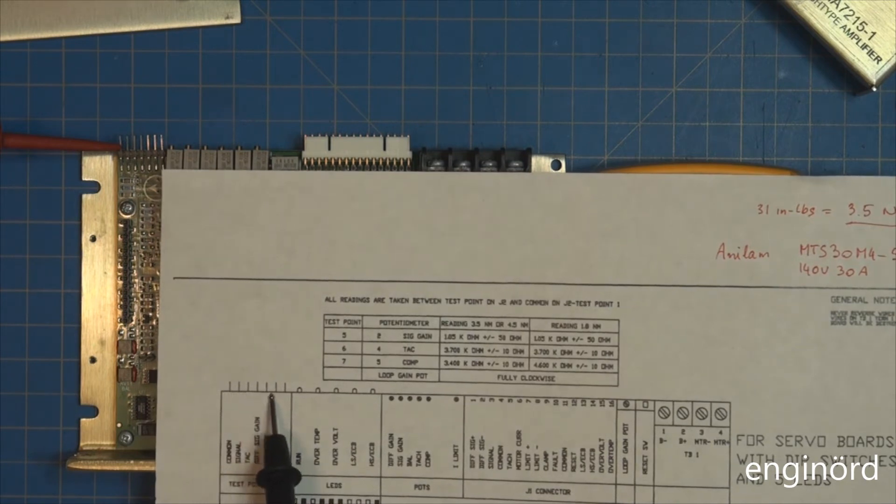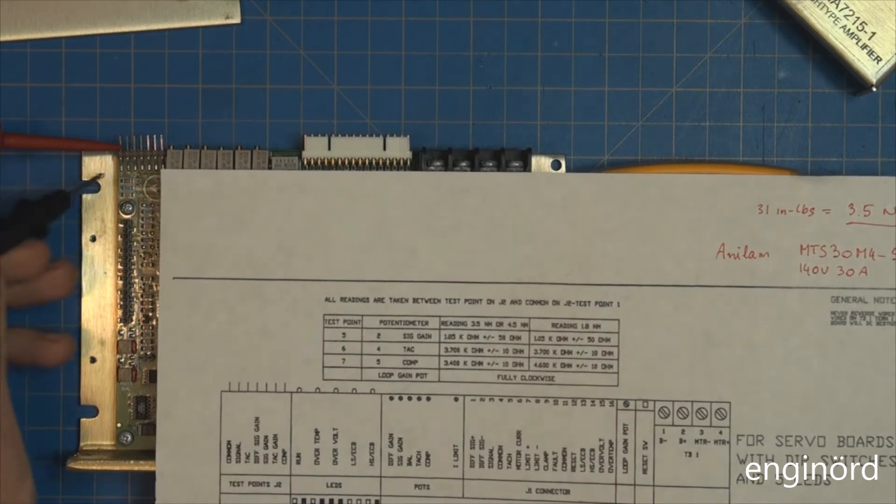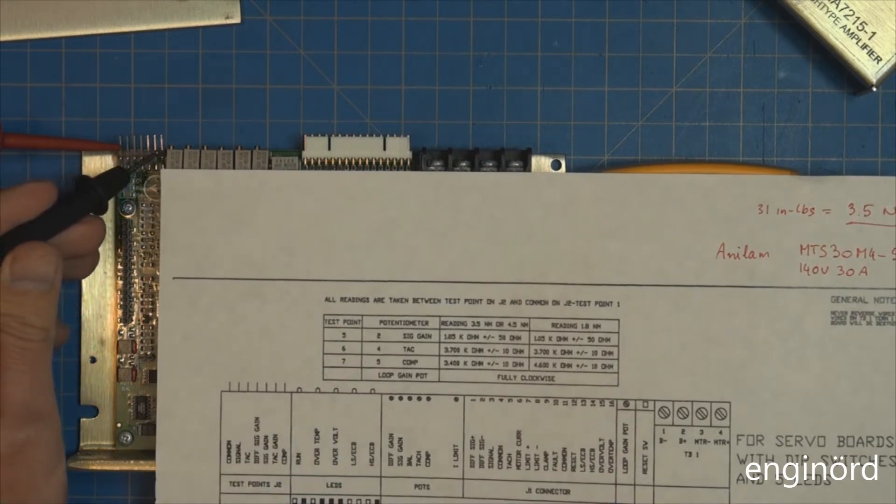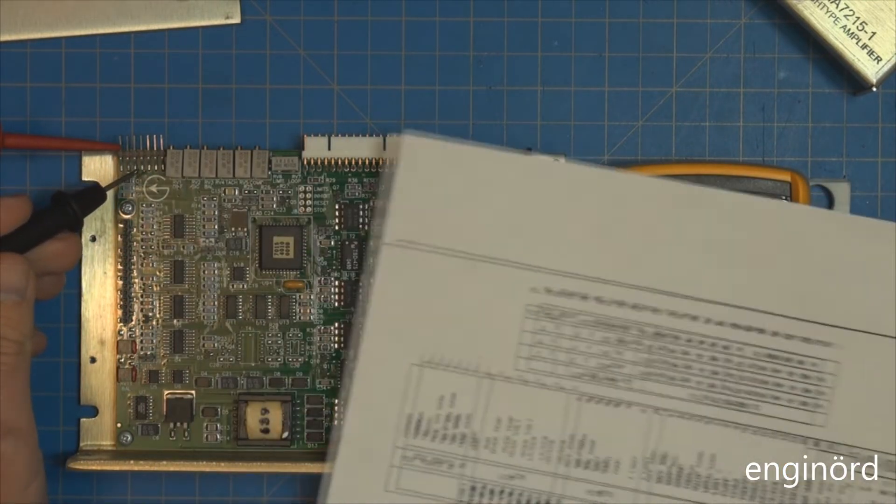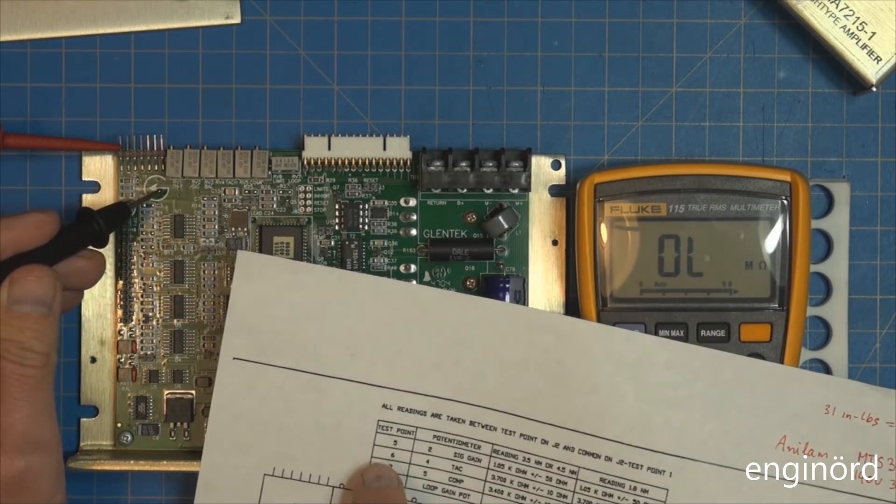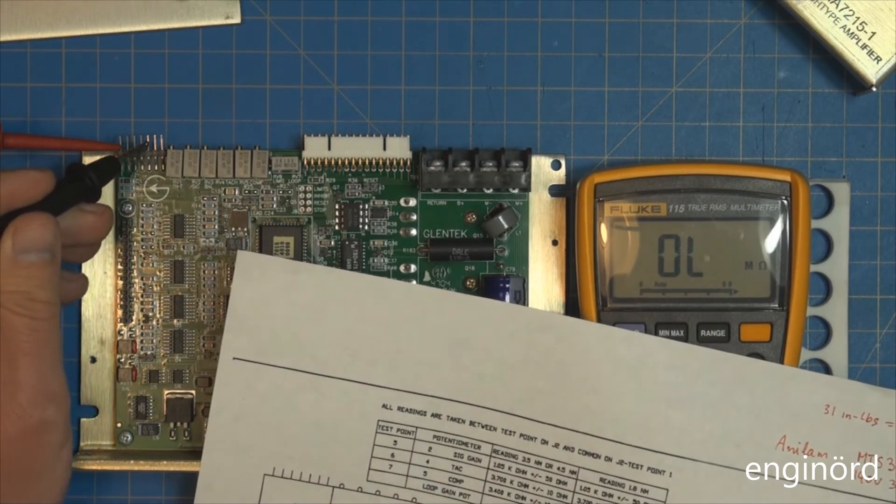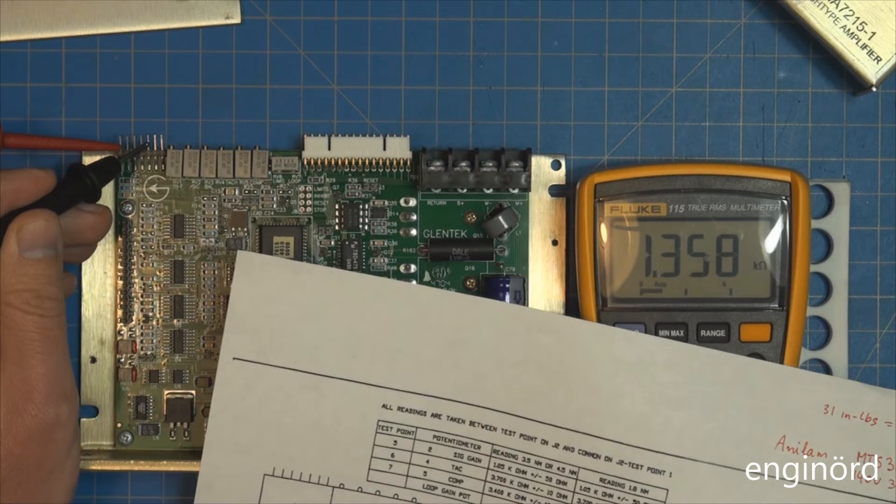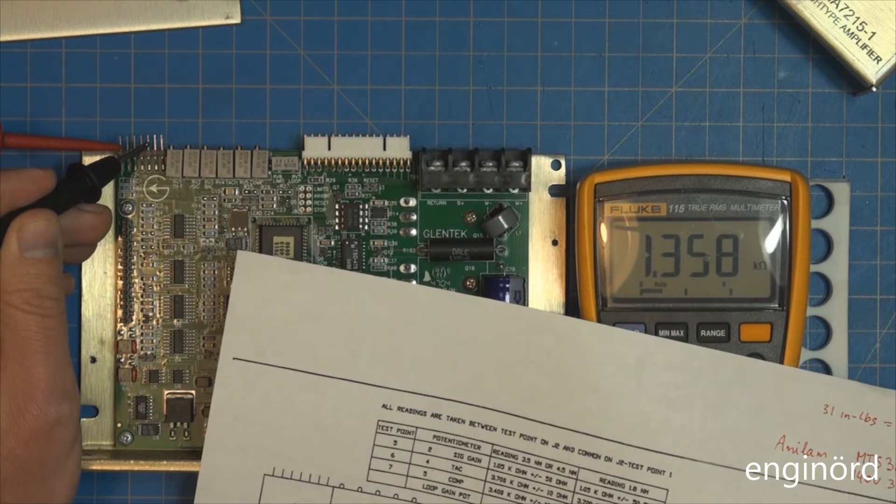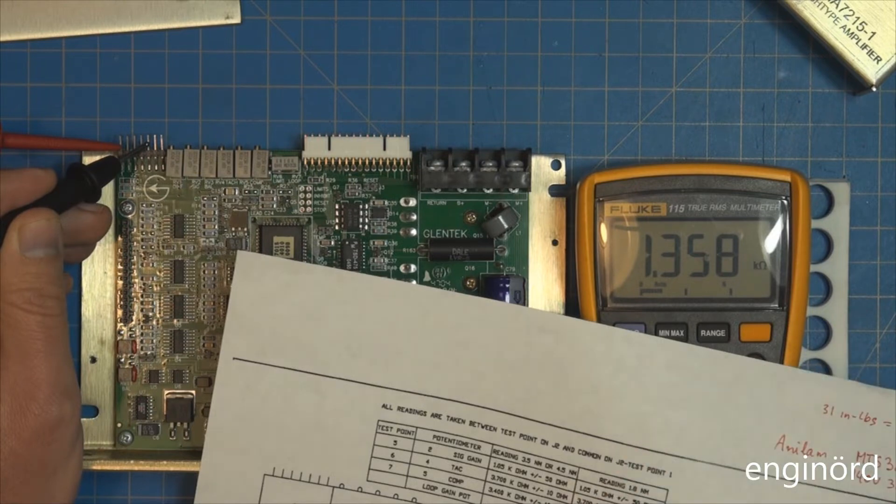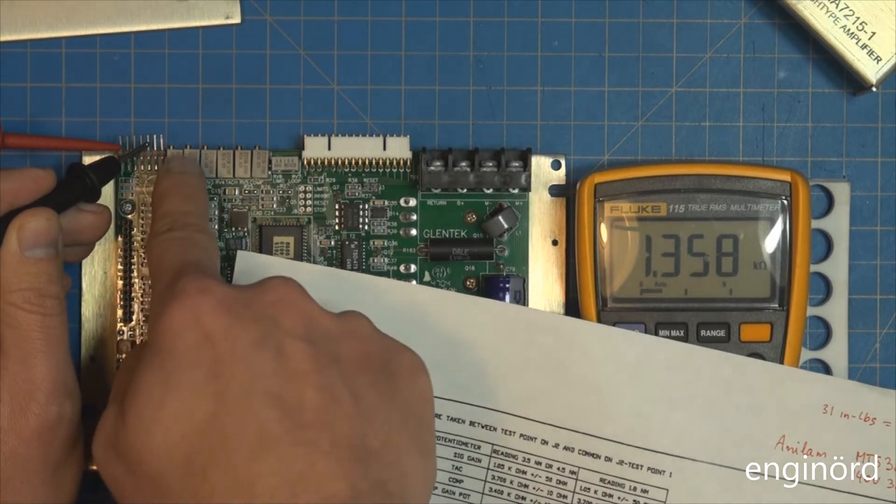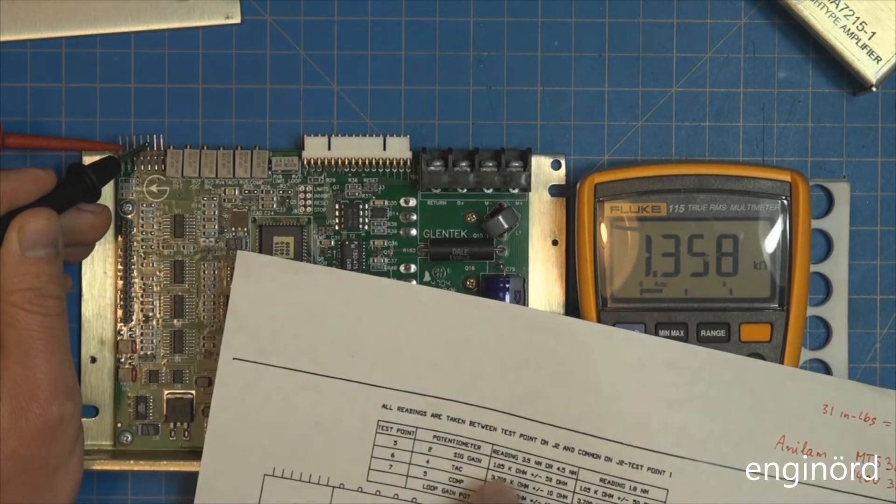The first one says test point 5, which is number 5 here, supposed to be 1.05 kilohm. You can see it's 1358, so it's 1350 ohm and it should be 1050 ohm. We need to find the potentiometer which is number 2, which is right here, and adjust it so the reading matches that.